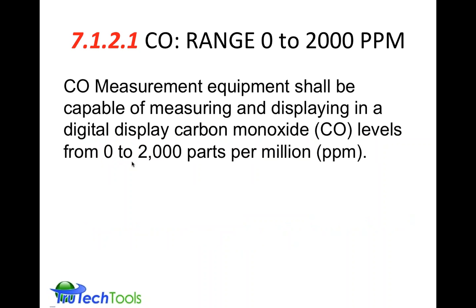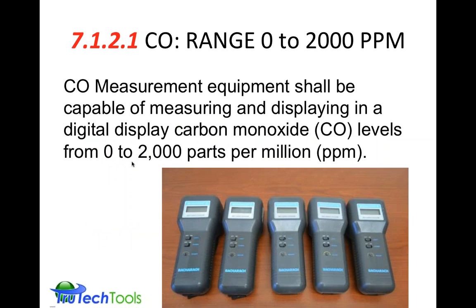Now, moving on to carbon monoxide, the 7.1.2.1 part of the standard calls for a range of 0 to 2,000 parts per million. So the equipment has to display up to that level. And it looks like someone has got a puppy farm going here raising Monoxer 2s. That was a product I was involved in developing at Bacharach. That's an older product. Even that product was available to display up to 2,000 parts per million. However, there are some additional requirements placed by the standard that would rule out products like the Monoxer 2 and its successors.